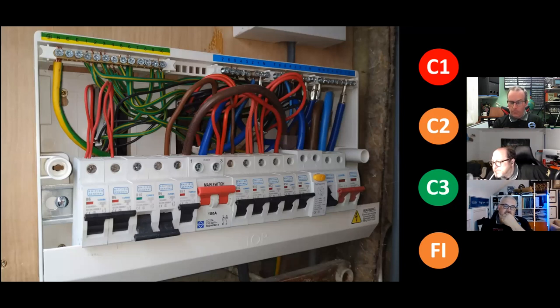Just on another note, John, the comments rightfully highlighted, where's the bonding on that? Well, the bonding may go down to the main earth terminal by the meter, in all fairness. A lot of them do that. They just have a CPC coming out the board. I'm not a fan of putting bonding into a domestic board. I would always rather have it on an earth terminal that's easy to disconnect with a tool rather than going into a live board. So for me, I don't put bonding in boards. It's always separate. But it depends on choice and accessibility and all the rest of it.